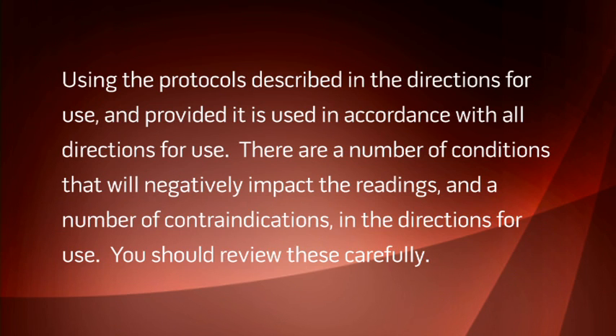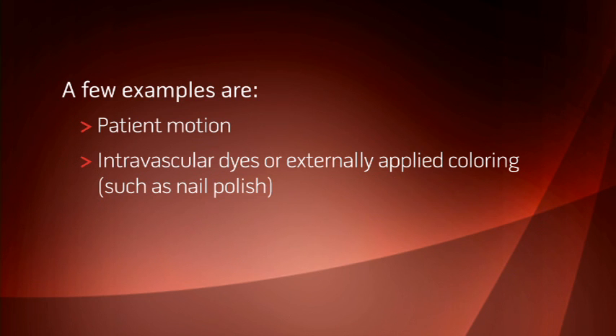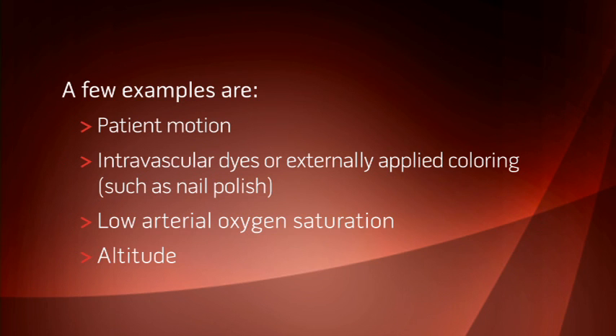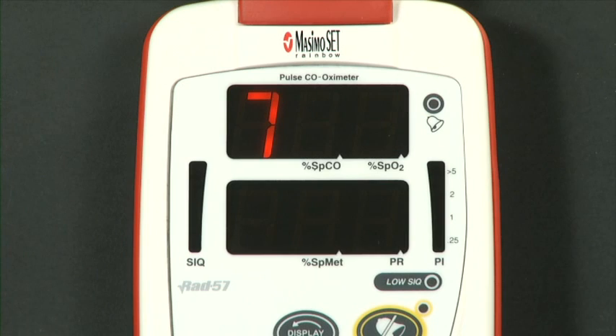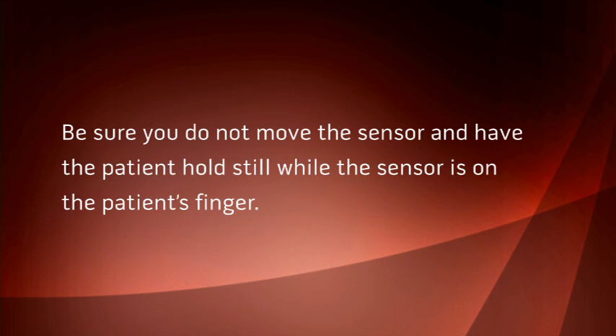There are a number of conditions that will negatively impact the readings and a number of contraindications in the directions for use. You should review these carefully. A few examples are patient motion and intravascular dyes or externally applied coloring such as nail polish, low arterial oxygen saturation, and altitude, all of which may lead to inaccurate SpCO and SpMet measurements. If bright light is interfering, the Rad57 will not leave the pulse search phase. It will appear as continuous spinning zeros on the display screen. Be sure you do not move the sensor and have the patient hold still while the sensor is on the patient's finger.